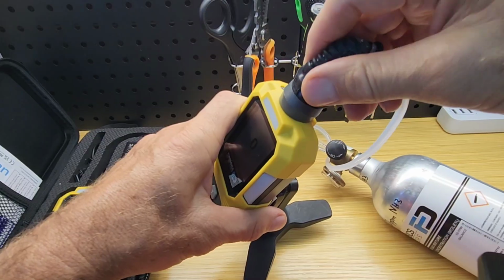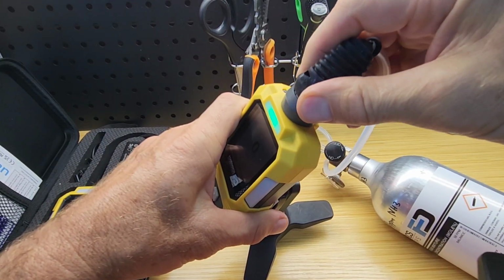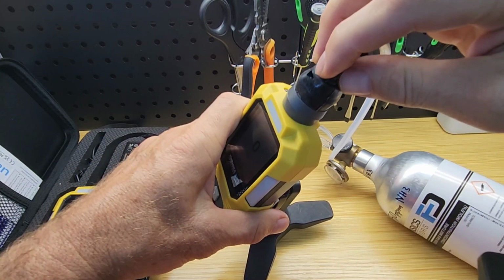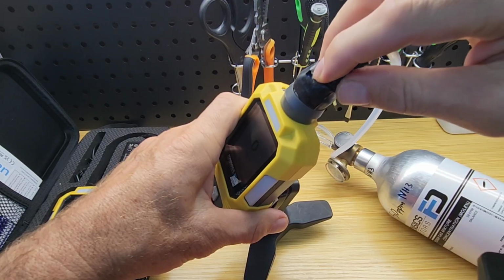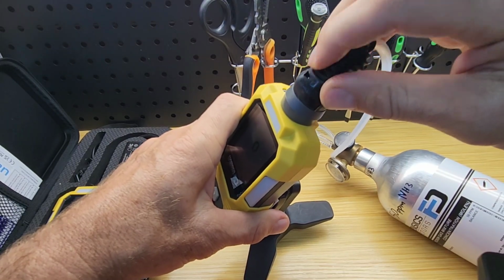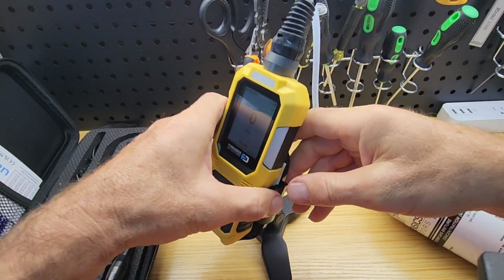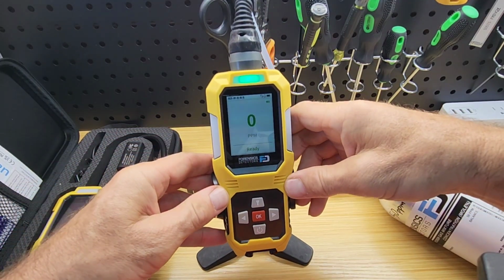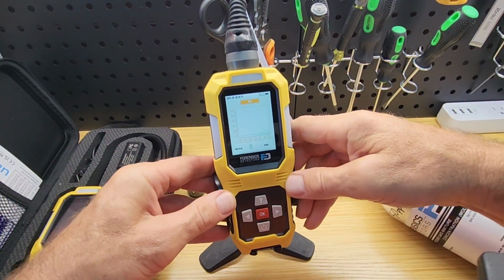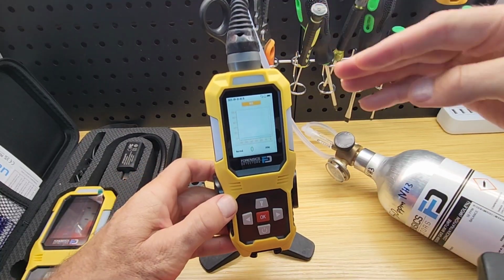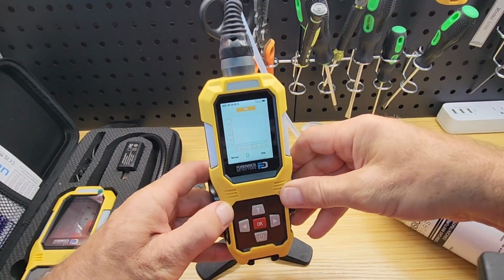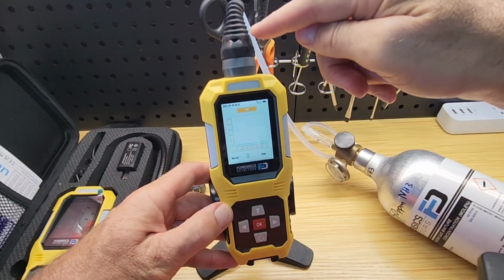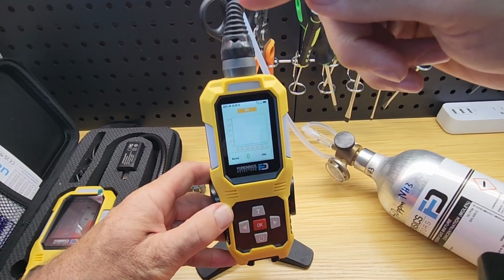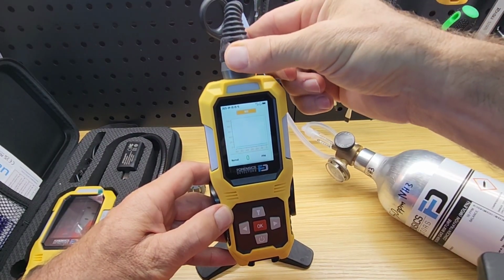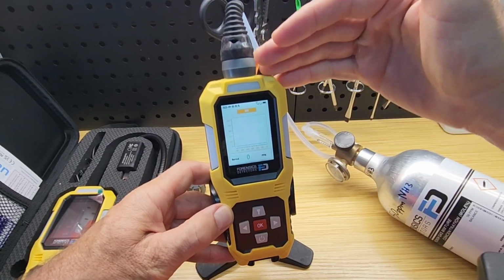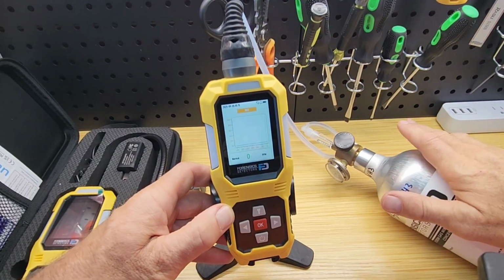Pretty simple. Now, you will notice that there is a little kink over here. That's deliberate. We at our factory here at Forensics Detectors have created this kink so that the pressure within this little chamber will not build up, will not increase beyond 1 atmosphere. Okay, folks? We don't want to pressurize this at all because then we're going to have other problems. So we want the air to come in, to circulate around, and to come out. Nice and easy, but the sensor will be exposed to positive pressure constantly. Therefore, we will not dilute the reference gas.